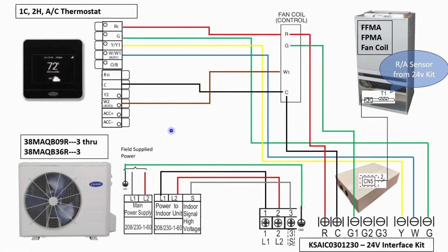I want to conclude the video by going over the wiring that's required in this installation. So we'll start with the fan coil. The fan coil is going to have 4 connections on it: R, G, W, and C. Our R is going to go to our thermostat R and also go to R on the 24-volt interface. The same is true for common. This is going to provide power to the 24-volt interface and the thermostat.